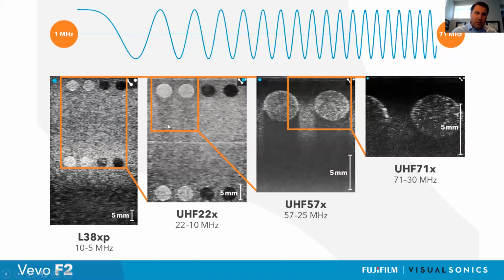If we take a region of interest and just zoom in, now taking the UHF-22X, this is the 22 to 10 megahertz, we can see much clearer resolution and delineation of these regions of the cyst. However, we are starting to lose some of the imaging depth. If we zoom in even further, now we're looking at the UHF-57X. This is all the way up to 57 megahertz, starting to see much more detail around these inclusions within the phantom. However, we are getting some more attenuation at these higher frequencies, and the imaging depth is now starting to be limited. So again, this trade-off between depth and resolution.